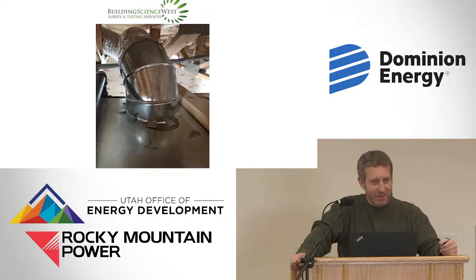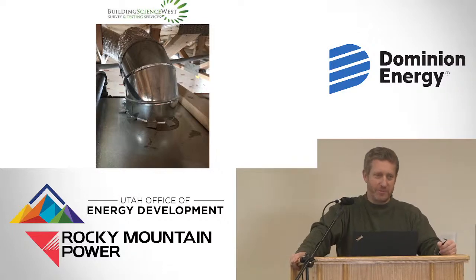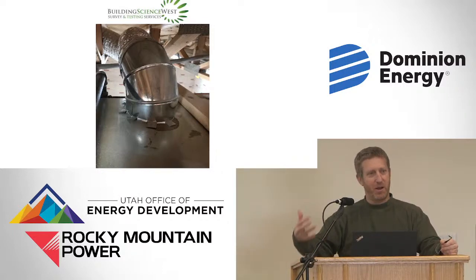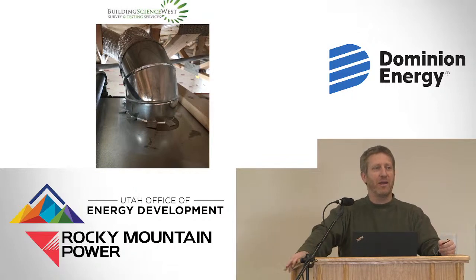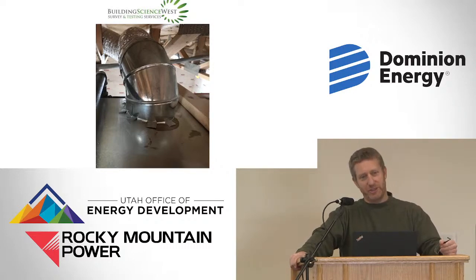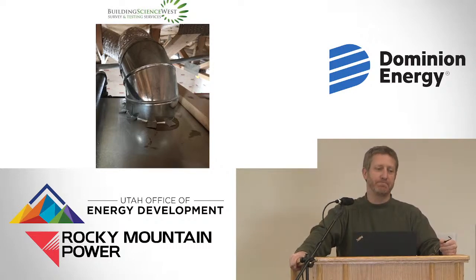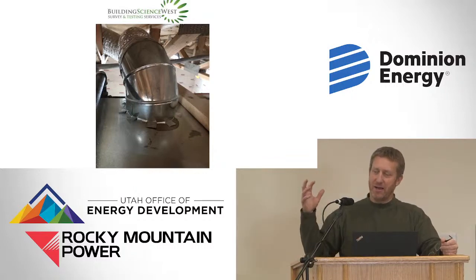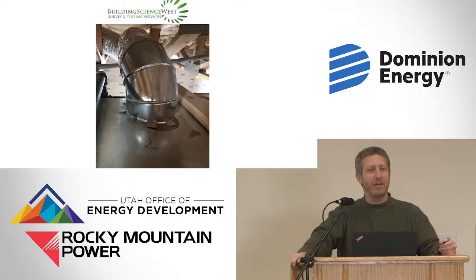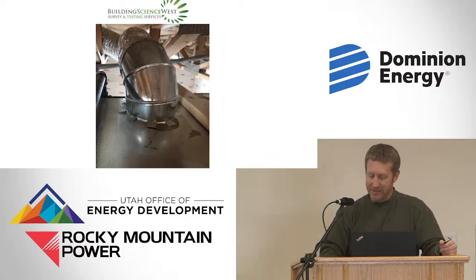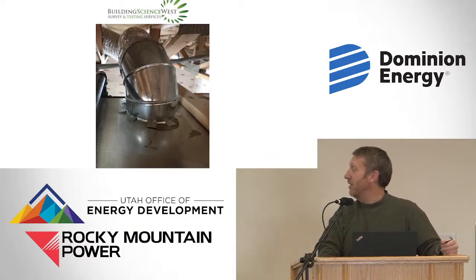But having leaky ducts and or leaky returns, because the supply side is positive pressure and the return side is negative pressure, if you have leaks in those you can put rooms in the home under positive or negative pressure, and that can create driving forces that push moisture into walls. In cold climates, moisture in walls is a bad thing, it condenses, and then bad things happen. So there are plenty of reasons why that doesn't and shouldn't meet code.